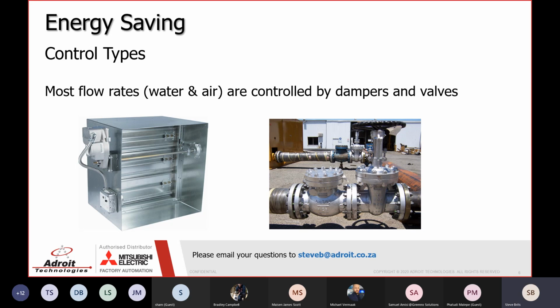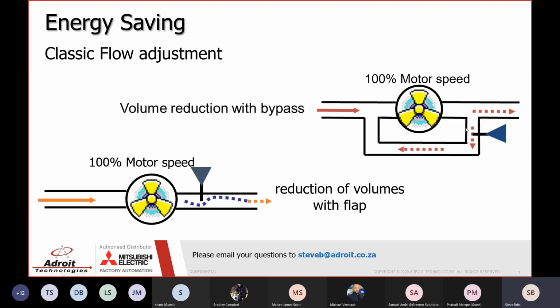Now, using a direct online or a star delta controller, your motor starts up, goes to 50 Hertz, and continuously runs at 50 Hertz. And if you need to control the airflow or the water flow, you're going to install a valve to control the water, or you can install dampers to control the airflow. A classic flow adjustment is a volume reduction bypass, which is shown in the top right corner, running at 100% motor speed, or just a normal valve also running at 100% motor speed.